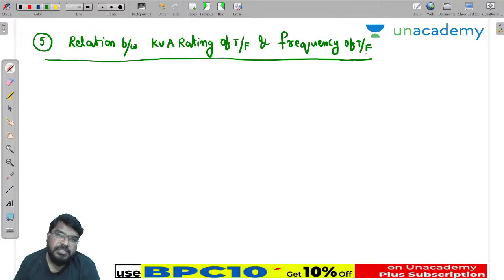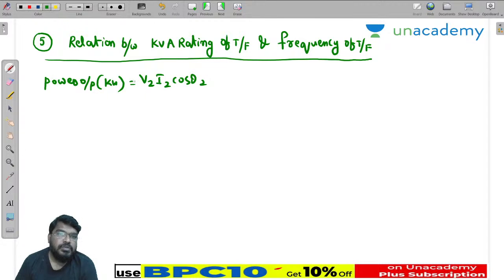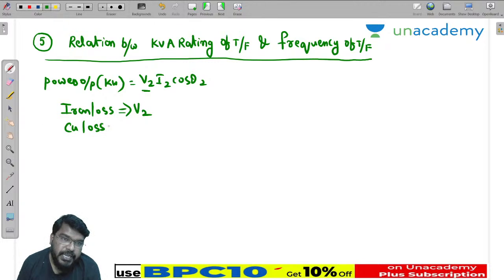KVA rating means the transformer rating is always mentioned in apparent power instead of active power. The reason is that the rating of any electrical machine depends on temperature rise. For example, power output in watts or kilowatts is V2 I2 cos theta 2. Here, iron loss depends on the voltage rating, whereas copper loss majorly depends on the current I2.